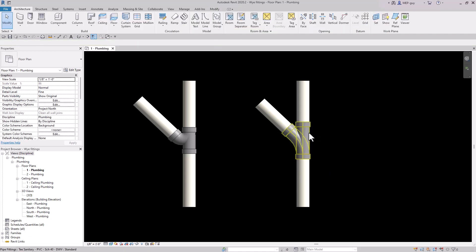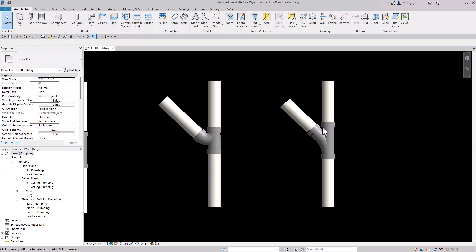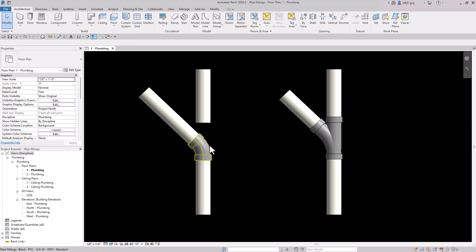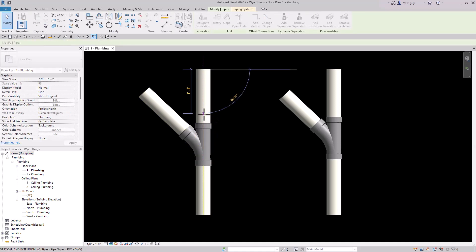Now this is actually not a Y fitting — this is actually a sanitary tee. If you ever have this issue, the easy fix is to delete it, trim one piece into the other, click on the fitting, click the little plus, and it will create a Y fitting. But then you have to reconnect the piping. That's a lot of steps, and honestly using the sanitary tee is not really ideal for modeling inside Revit.